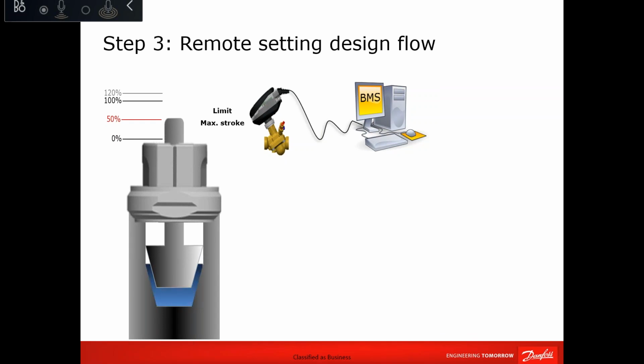Which means if you have a loop of 32 actuators linked in one floor DDC, then once you access the BMS, we have a tool which is called the Danfoss configuration tool. Having this tool will allow you to make a CSV format. The CSV format will look like Novocon ID, which is unique to every Novocon. So you have your IDs in your loop, in front of it, comma, then you put your flow rate. Once you're done with it, this is also done by Danfoss, which we can do for every project. You feed the total design flow into your loop. So let's say the whole project can be set from your computer by simple uploads. So this is the real feature and benefit of the design flow setting remotely. It's not only one by one, you can set the whole project from the same location, as long as you have the communication live everywhere.